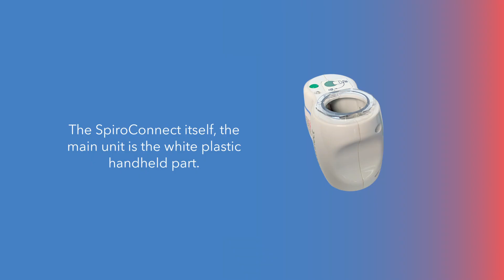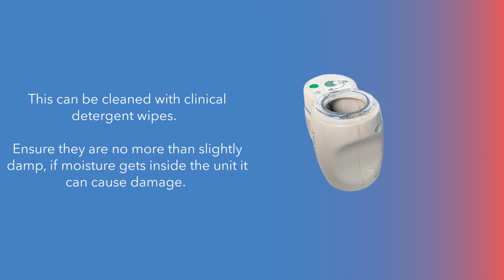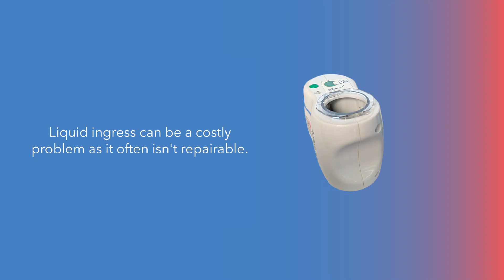The SpiroConnect itself, the main unit, is the white plastic handheld part. This can be cleaned with clinical detergent wipes. Ensure they are no more than slightly damp. If moisture gets inside the unit, it can cause damage. Liquid ingress can be a costly problem as it often isn't repairable.